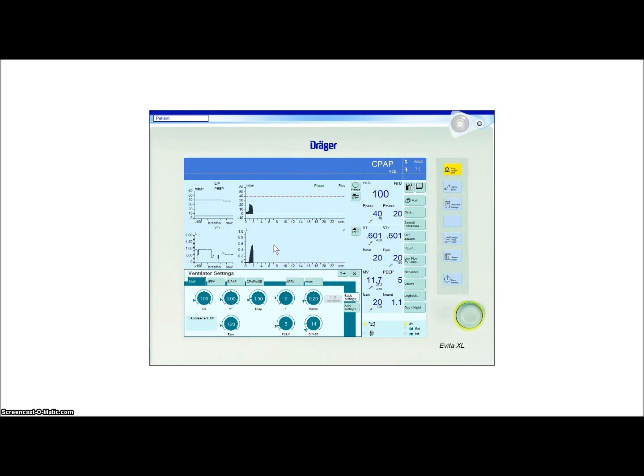This is also used, more in the ICU, on people on ventilators. CPAP is where the patient gets a continuous pressure. I'm going to turn pressure support off for a minute. The machine gives continuous positive airway pressure, and it helps keep the lungs and the airways open when you breathe out. PEEP is another name for CPAP. In a mandatory mode where the ventilator does give breaths, such as SIMV or IPPV, it is considered PEEP, positive end-expiratory pressure.